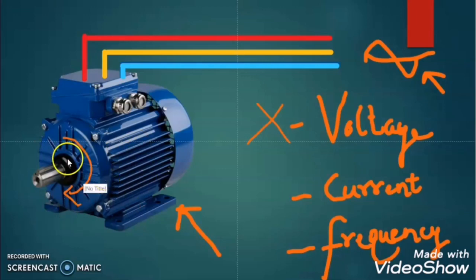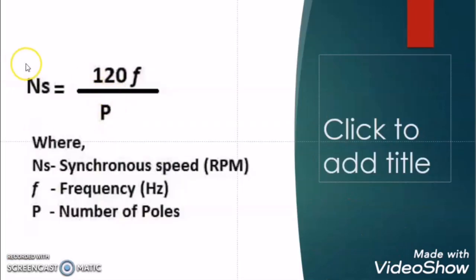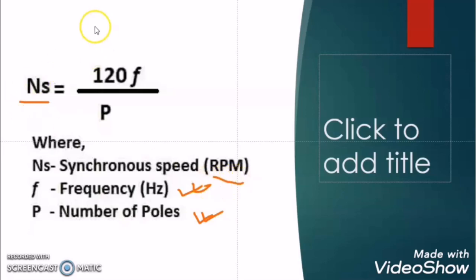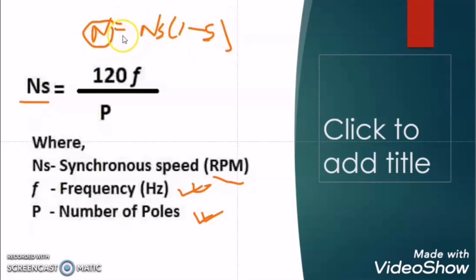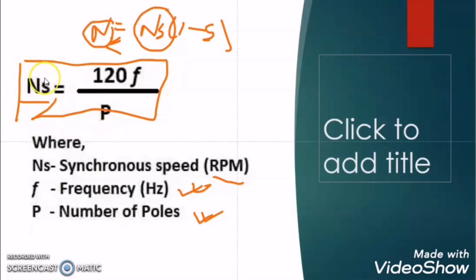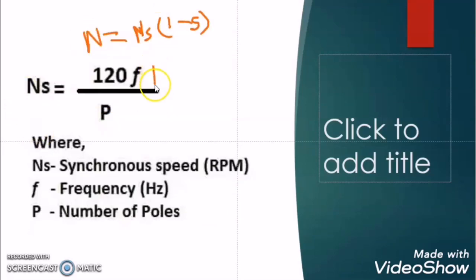Now let us move to the next method. As we know, the synchronous speed is given as Ns = 120f / p, where f is the frequency in hertz and p is the number of poles. The rotor speed N = Ns × (1 − s). The rotor speed is directly proportional to synchronous speed, so if we change the synchronous speed we can control the rotor speed. By increasing and decreasing the supply power frequency we can control the synchronous speed and accordingly control the rotor speed.